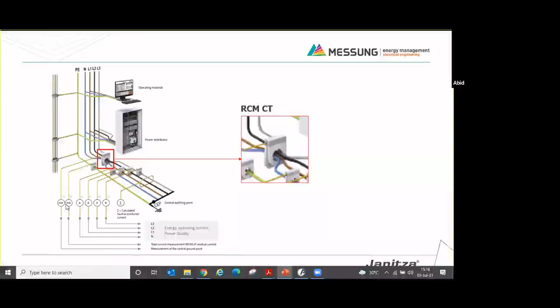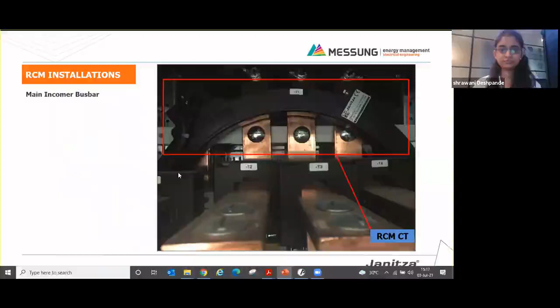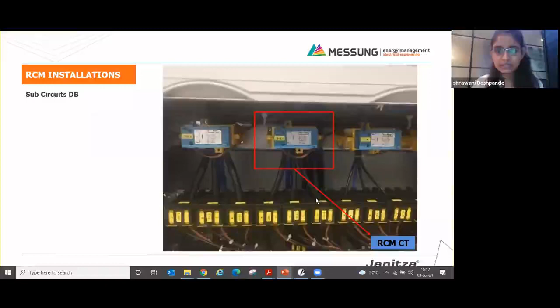Now these are some of the actual locations where the CBCT is installed. As you can see, this is the main incomer bus bar. So these are the individual bus bars. On these, individual CTs are put, and this complete big one is the CBCT, which is used for residual current monitoring. Then this is the sub-distribution board. As you can see, there are 3 different RCM CTs, and through each CT, separate phase conductors are going, and these are the individual CTs put on the individual conductors.